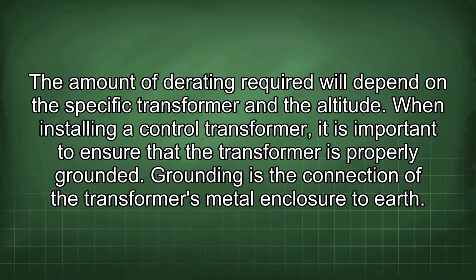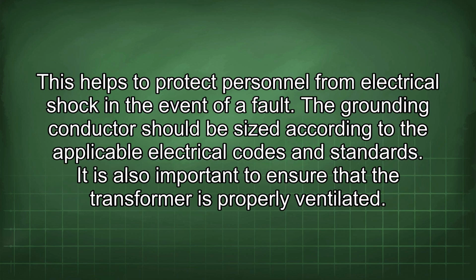When installing a control transformer, it is important to ensure that the transformer is properly grounded. Grounding is the connection of the transformer's metal enclosure to earth. This helps to protect personnel from electrical shock in the event of a fault. The grounding conductor should be sized according to the applicable electrical codes and standards.